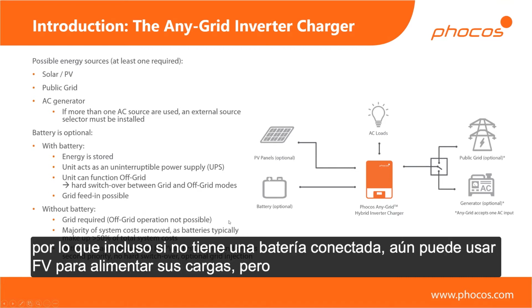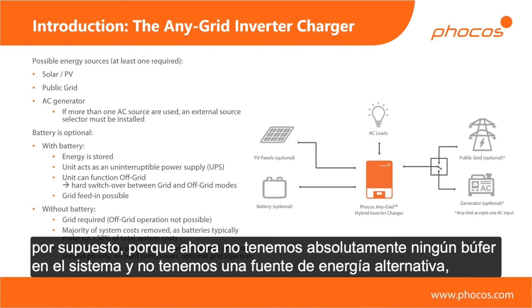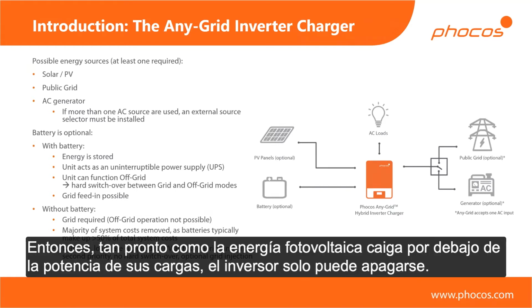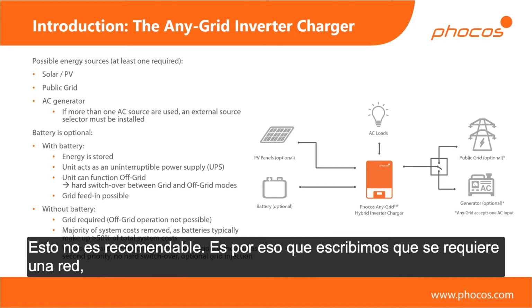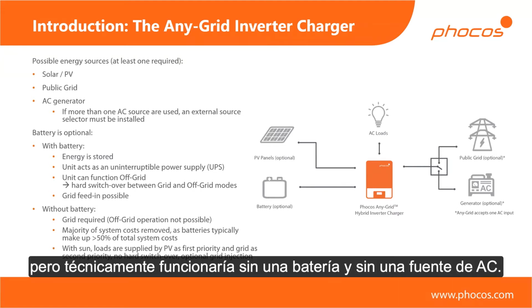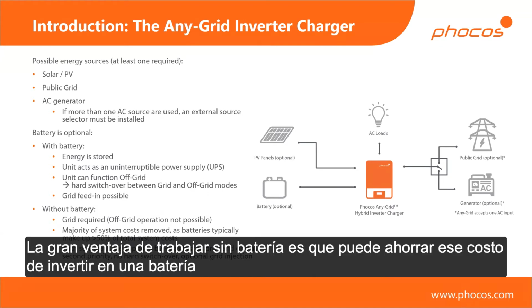Even if you have no battery connected, you can still use PV to power your loads. But because we now have absolutely no buffer in the system and no fallback energy source, if we don't have a grid connection, then as soon as the PV power drops below the power of your loads, the inverter can only turn off. So this is not recommended. That's why we write that a grid is required. But technically speaking, it would work without a battery and without an AC source. The big advantage of working without a battery is that you can save the cost of investing in a battery.